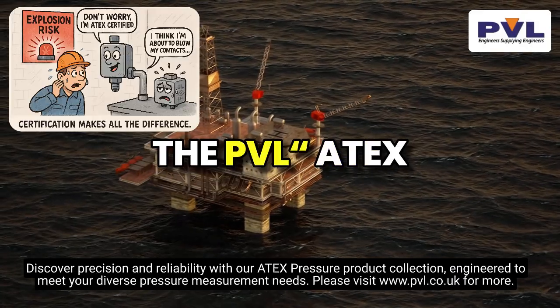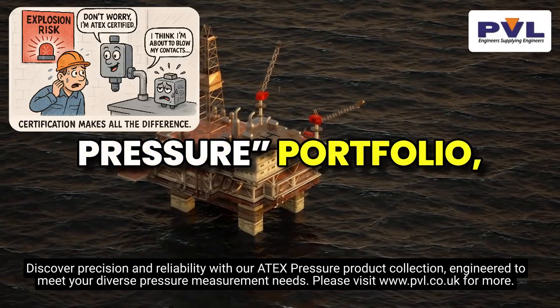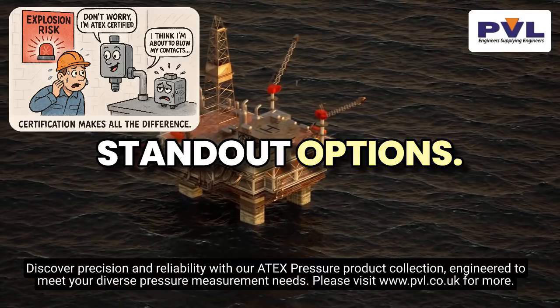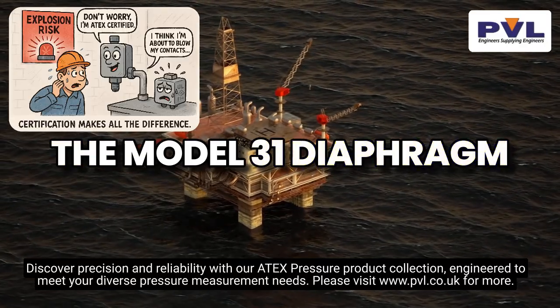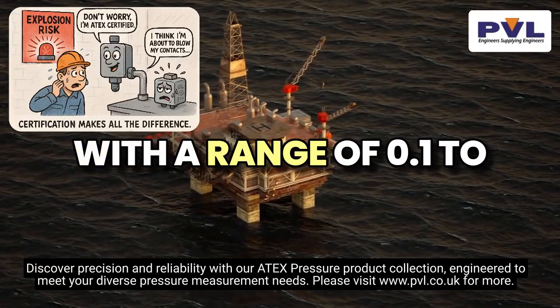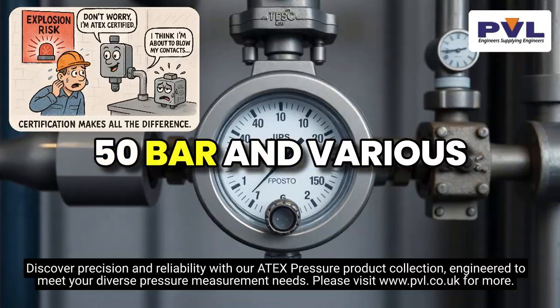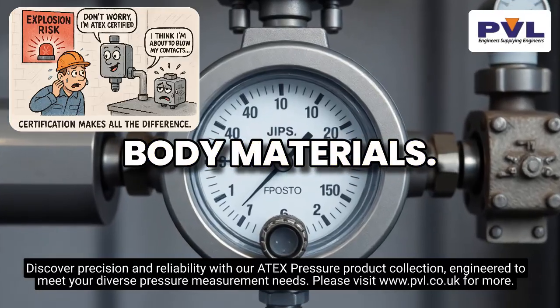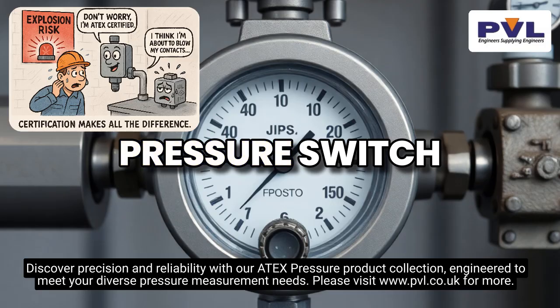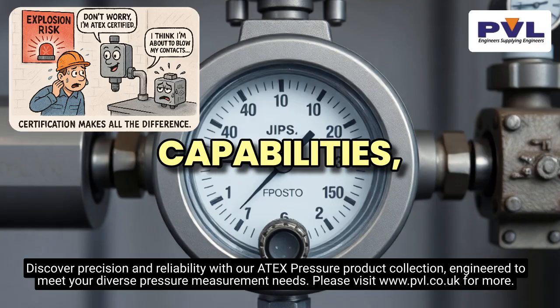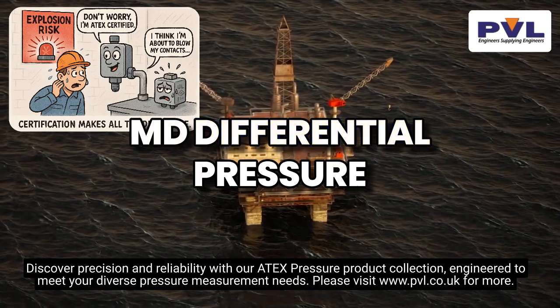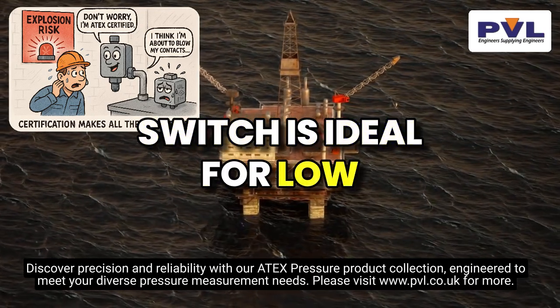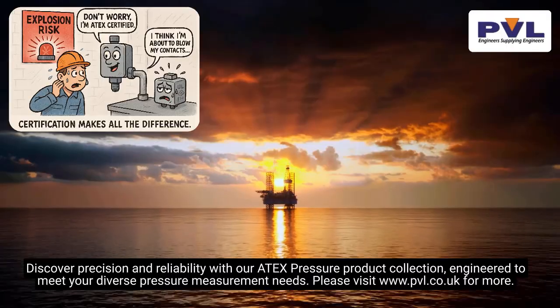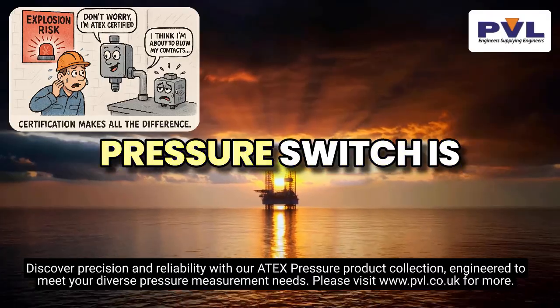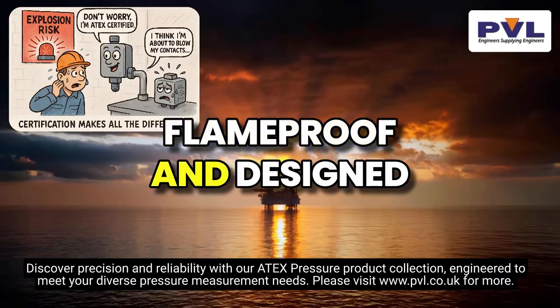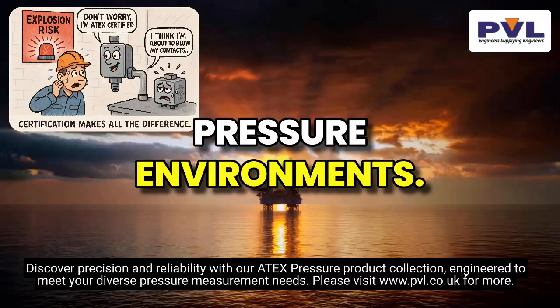When it comes to the PVL ATEX pressure portfolio, there are several standout options. The Model 31 diaphragm pressure switch is versatile, with a range of 0.1 to 50 bars and various body materials. The Model 48 piston pressure switch offers higher pressure capabilities, while the Orion MD differential pressure switch is ideal for low differential pressure applications. The Orion FC compound pressure switch is flame-proof and designed for high-pressure environments.